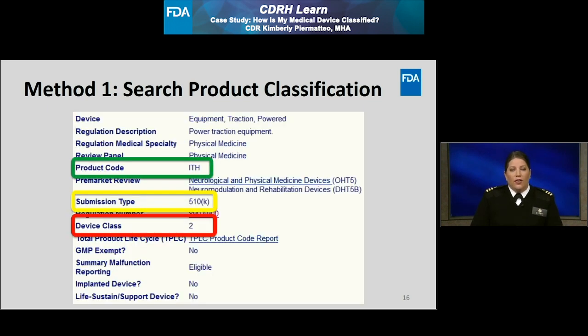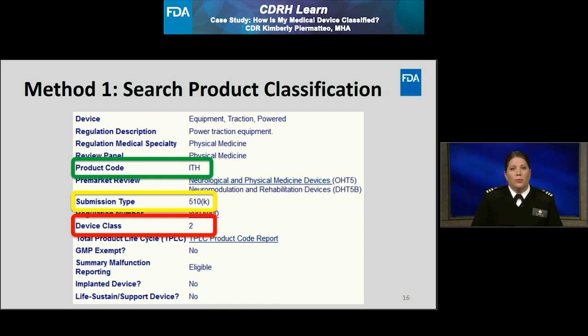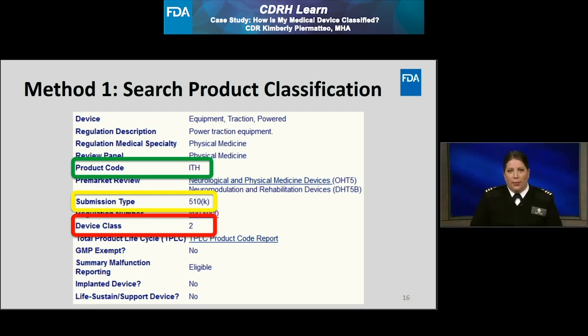Going back to the screenshot for the ITH product code in the public product classification database, I can then determine what regulatory requirements apply to this powered traction device. I can see on the screen that the submission type for a powered traction equipment device is 510K, which is highlighted in yellow on the slide, which means I would need to obtain 510K clearance prior to marketing this device. Additionally, this type is considered to be class 2, which means general controls apply as well. If there were any special controls for this device type, I would have been able to review them as part of the regulation description.